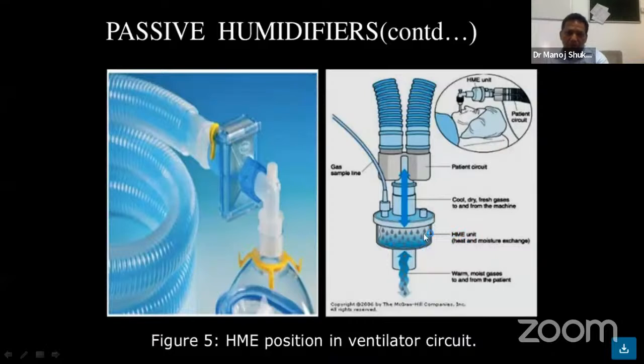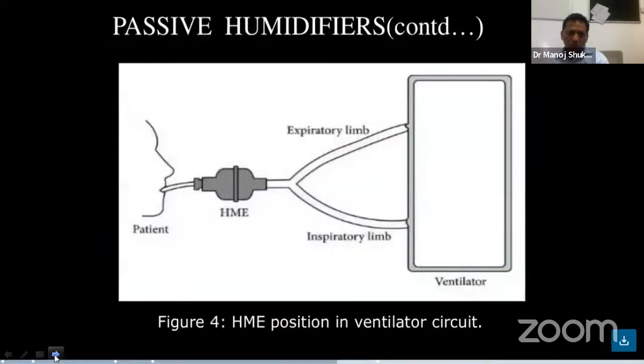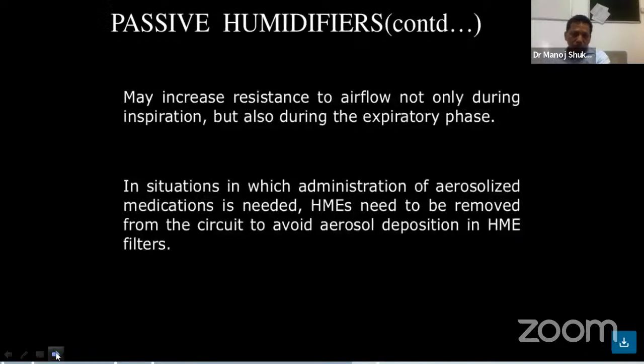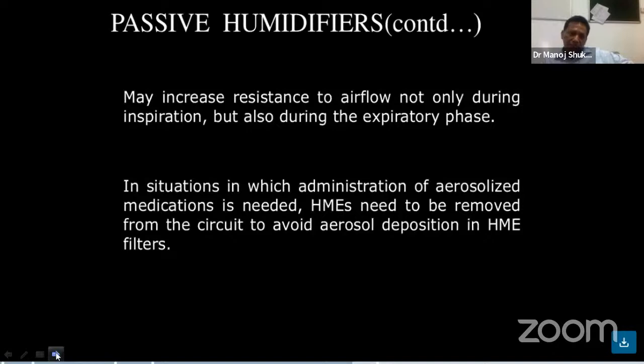The HME is placed between the endotracheal tube and ventilator tubing. Passive humidifiers may increase resistance to airflow not only during inspiration but also during expiration. In situations where aerosol medication administration is needed, the HME needs to be removed from the circuit to avoid aerosol deposition in the filter. These are some drawbacks of this filter.